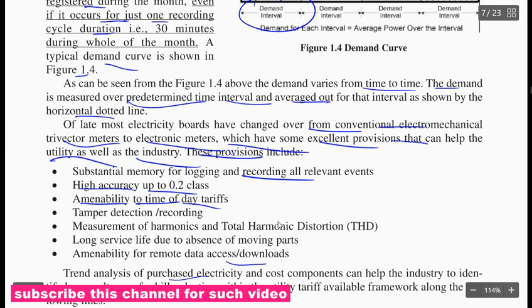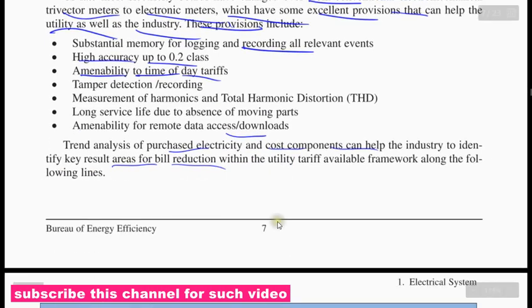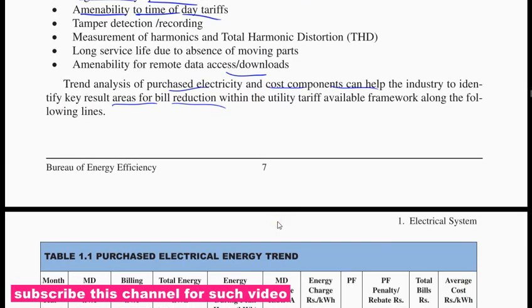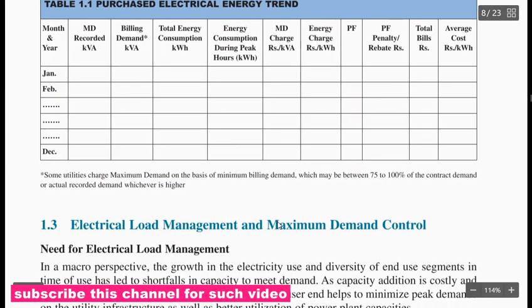Trend analysis of the purchased electricity cost components can help the industry identify key result areas for bill reduction with the utility and tariff, along the following lines: the purchased electrical energy trends, that is MD recorded kVA, billing demand, total energy consumed, energy consumption during the peak hour, charge per kVA, MD charge, energy charge per kWh, power factor, penalty rebate, total bills, average cost.